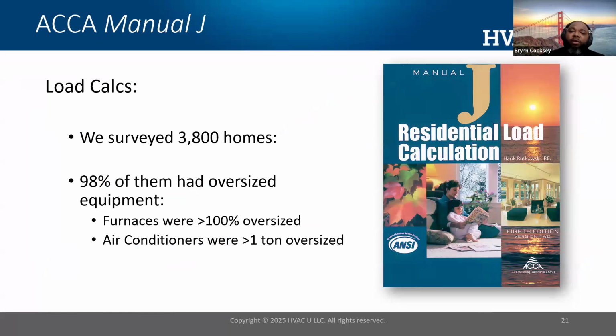Now, we have heard some horror stories about rapid heat pump adoption, and a lot of those horror stories come from the simple fact that when we were using forced air heating and cooling systems that use combustion appliances such as a furnace, that furnace has such a high delivery air temperature that it masks a lot of our design mistakes. Right. So you can have a furnace that wasn't sized properly, that was not commissioned properly, but just because it delivers such a warm air temperature to the space, oftentimes the customer still experiences a relative level of comfort. However, was it perfect? And the answer is no.